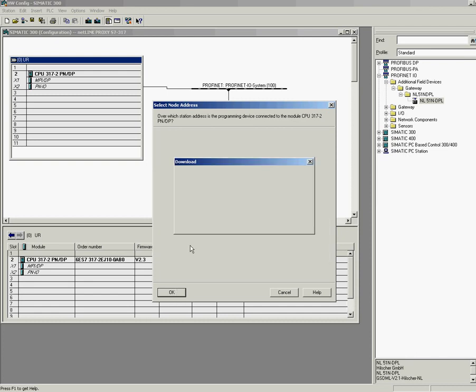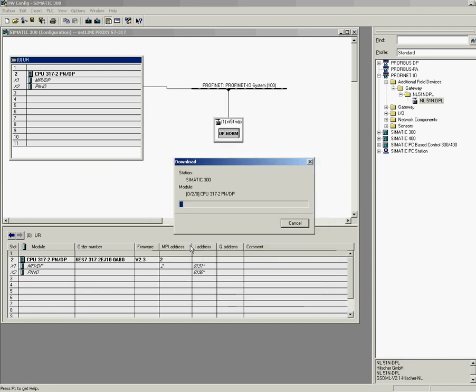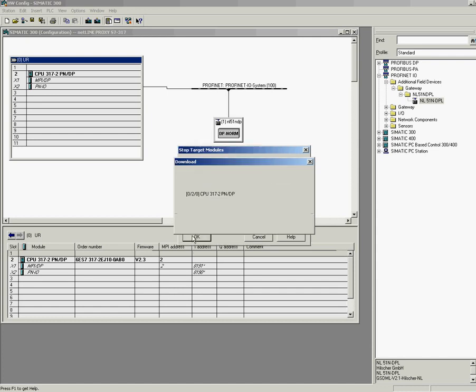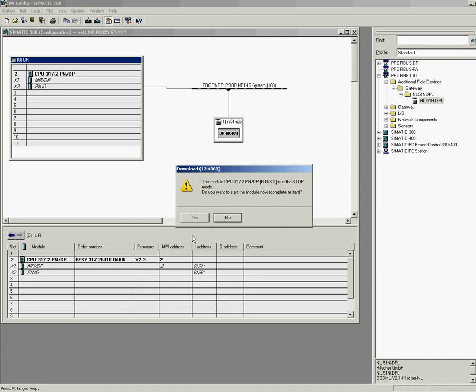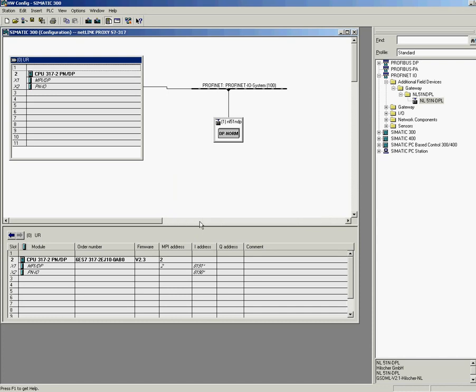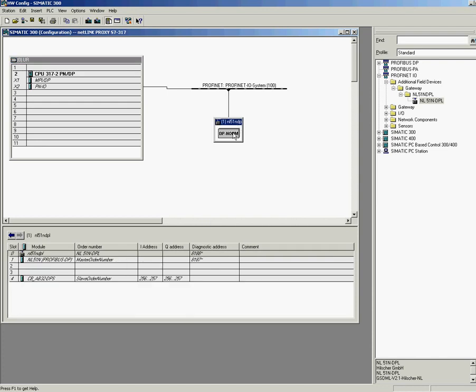Press OK here. Now it will make the download. And after the PLC is configured, hopefully my LEDs are all getting green now. Yes, go into run mode. And booting. Yes. OK, now I see all my LEDs are green on my PLC. So it is communicating with the Netlink.